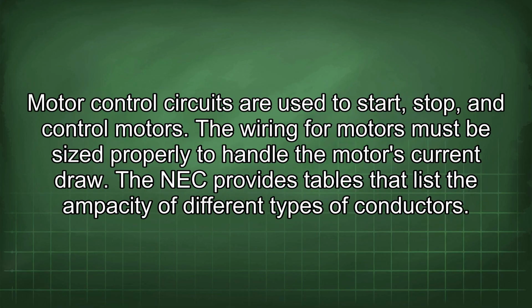Motor control circuits are used to start, stop, and control motors. The wiring for motors must be sized properly to handle the motor's current draw. The NEC provides tables that list the ampacity of different types of conductors.